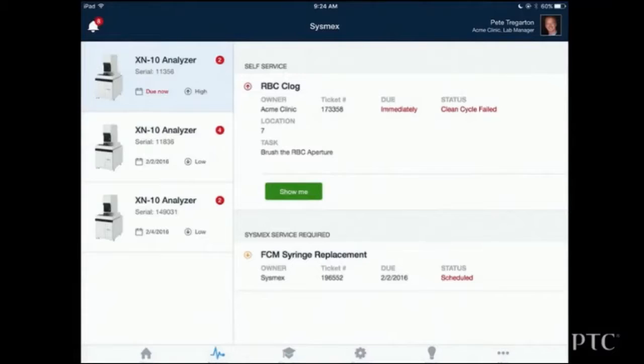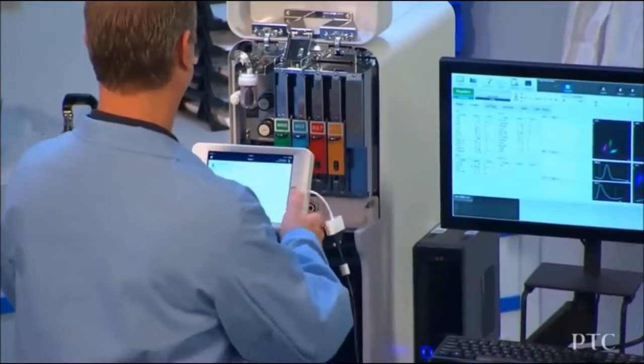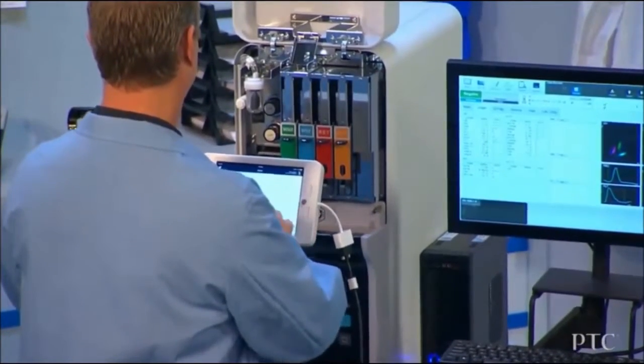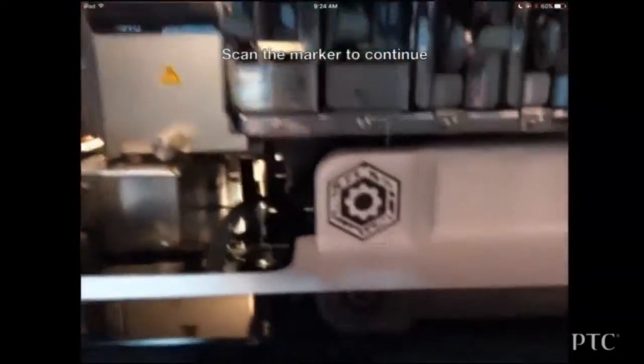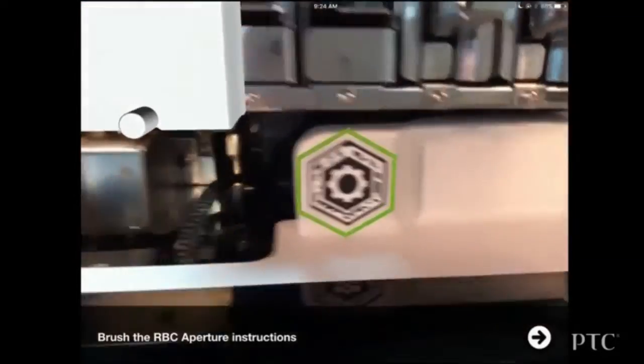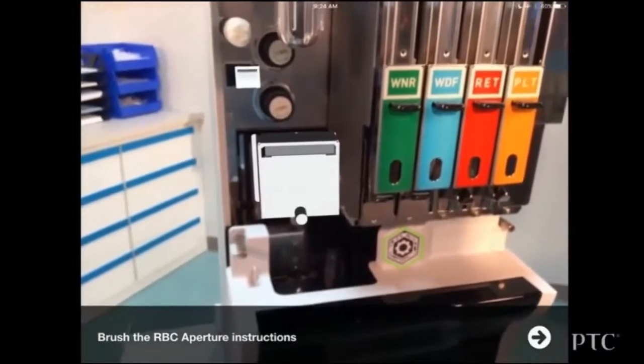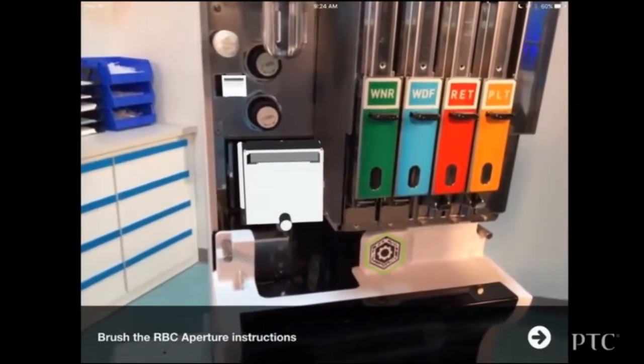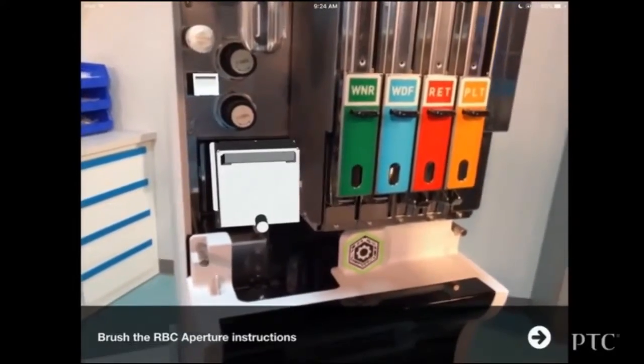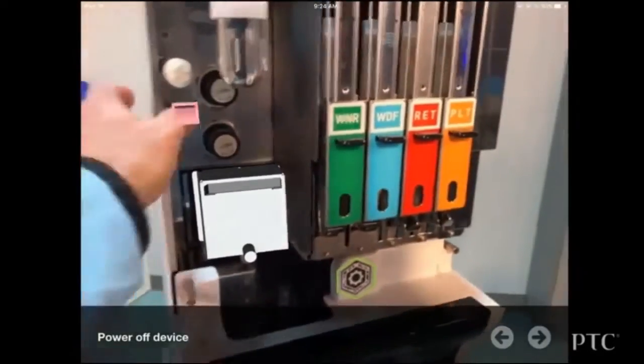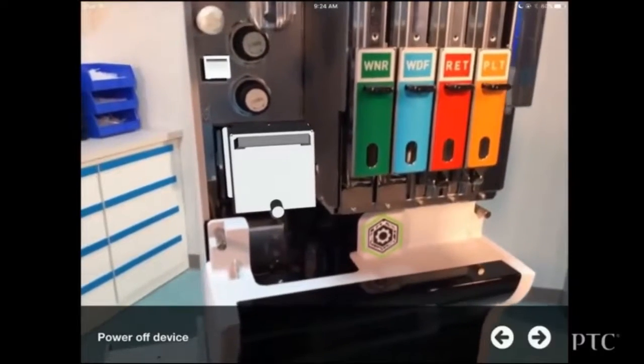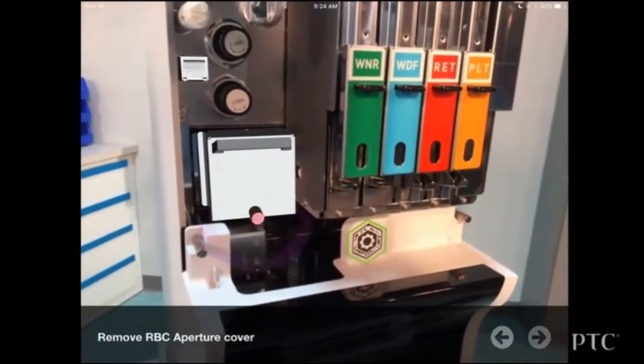Well, it's evident here in real time that the automated clean cycle was not able to resolve this clog. So Pete's next task is to perform a manual cleaning, which he really doesn't do very often. So this is the perfect place for augmented reality assistance. So Pete opens the front lid of the analyzer to get to the AR marker on the device. The first step in seeing the augmented reality overlaid on the analyzer is to scan the marker with this My Sysmex iPad. Here we see that Pete needs to power off the analyzer before he can continue. So the My Sysmex application confirms that the analyzer is powered off.